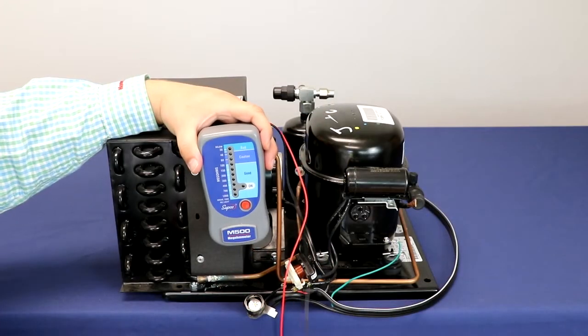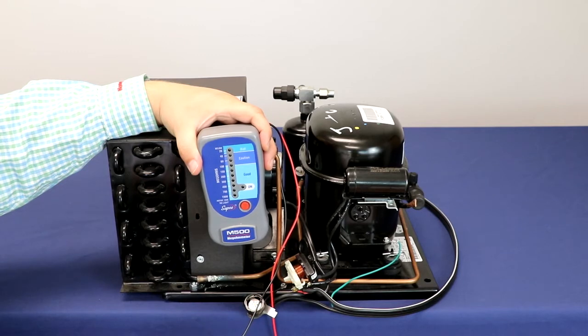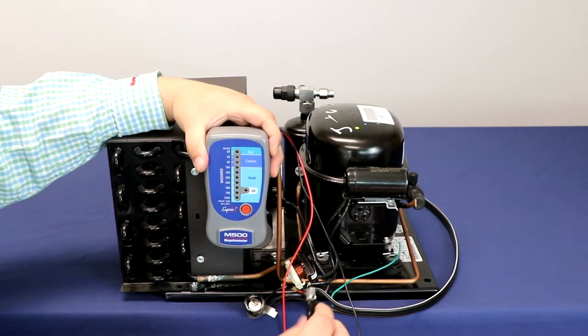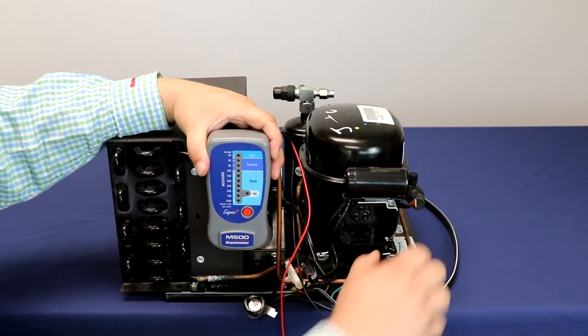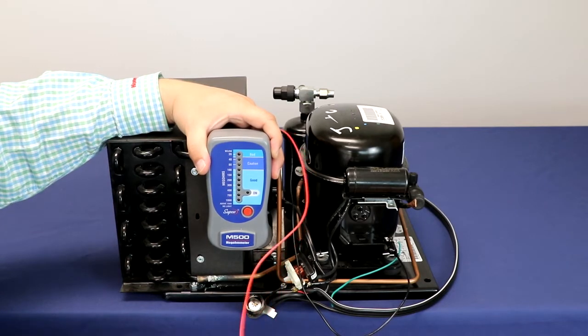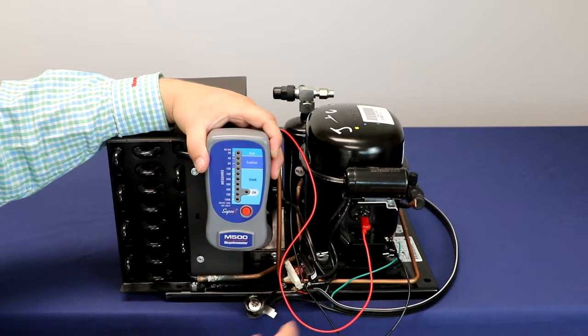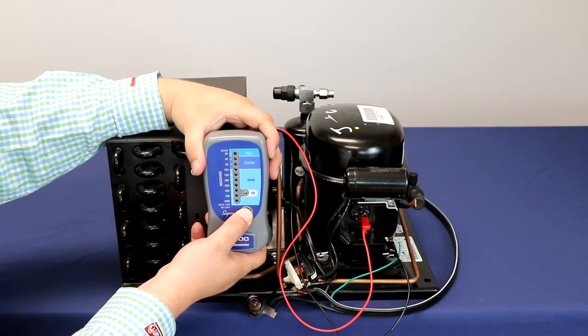Here we have our Supco M500 megaohm meter. In order to check your compressor or your motor winding properly, you will need to take one of your leads, put it onto your ground or the casing or the insulation, depending on what you're using. Then take your other lead and go to the winding.